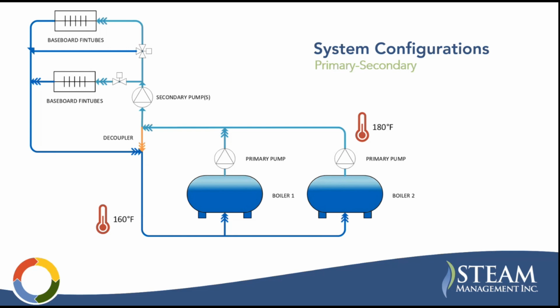Also, I should point out there can be a different combination of VFDs on these pumps. You can have primary constant, secondary variable, where your primary pumps are constant and secondary pumps are on variable speed. You can have primary variable, secondary variable, where everything's on VFDs. It depends. There are a lot of different sub-configurations off of these. I should also mention that off of these secondary loops, you can have tertiary loops. This can get pretty complicated if you have a lot of different zones. You can have a lot of different loops coming off of these loops.